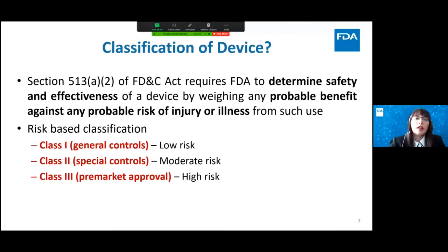And so FDA determines the safety and effectiveness of the device by weighing any probable benefit against probable risk. There needs to be more benefit than risk when we're evaluating devices. There are three levels of classification for the FDA under the FDA regulations. Class 1 devices are considered low risk. Class 2 devices are considered moderate risk, and class 3 are considered high risk. So that is the highest regulatory bar that we have within our regulations to regulate medical devices.